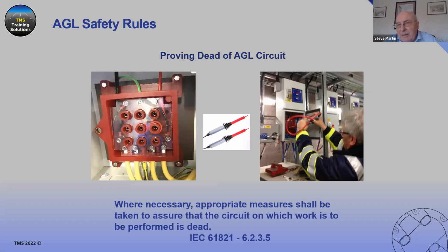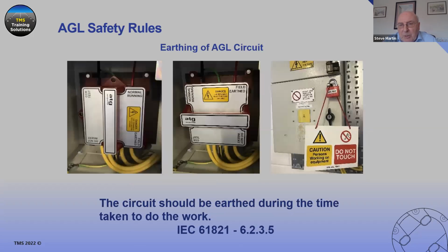We can safely test to prove it's dead. Once we know it's dead, we can move the link to the field earth position and put it back in. We've now earthed that field circuit, so we know our circuit is down to earth, and should be at zero potential or close to it.